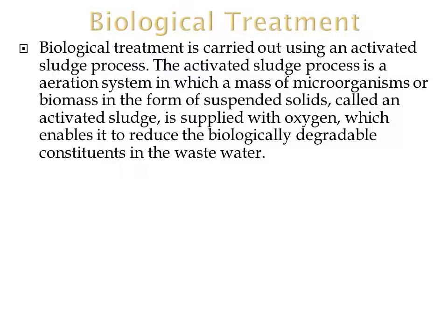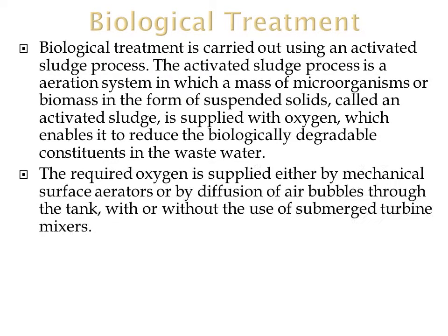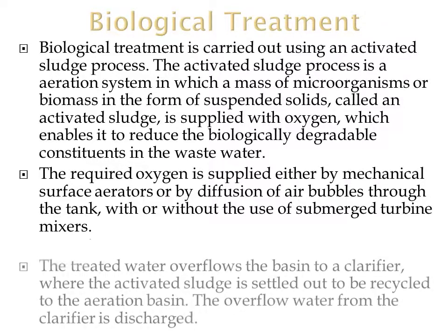That means the microbes that are present are activated by supplying oxygen, and the microbes degrade the organic compounds present in the wastewater in the presence of oxygen. The oxygen requirement is mostly supplied either by mechanical surface aerators, by diffusion of air bubbles through the tank, or by submerged turbine mixers.